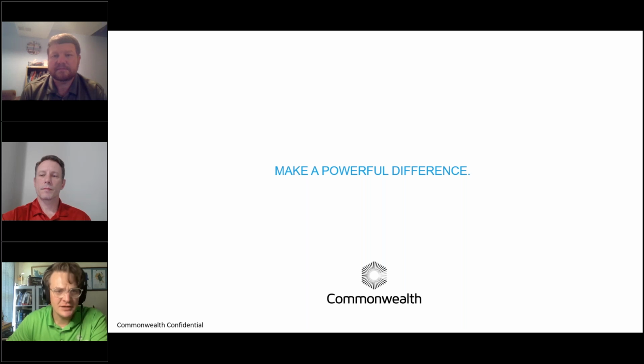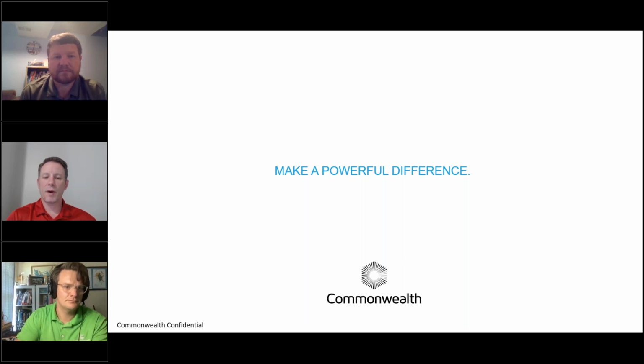Talking about mentioning conservative results, asking what method are you citing that is giving the conservative results? Chris, that was on your slides, I think. If we're talking about the DC results, that's all the formula from NFPA 70E. I think that's a pretty standard formula for the DC side. I don't think there's too many other methods for that. But how you come up with a short circuit current to put into that formula depends on whether you're doing the steady state or the transient analysis to get a lower fault current.